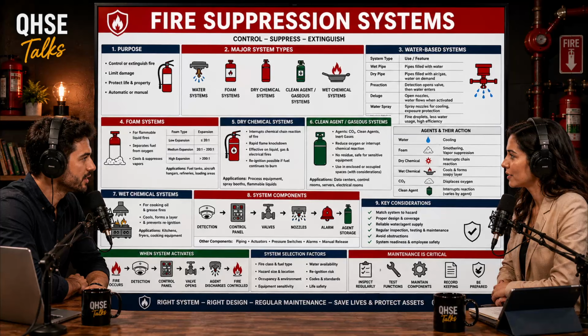And the second catch, the global one. The environmental impact. Halons are incredibly potent ozone-depleting substances. Because of this massive environmental threat, the production of new halon was completely phased out globally under the 1987 Montreal Protocol. So if I'm building a brand new data center today, I can't buy halon. What has the industry developed to replace it?